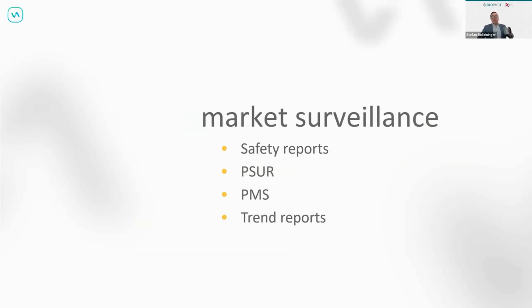So, next part is the post-market surveillance. Since the product is after the conformity assessment in the market, we need to talk a lot about the post-market surveillance system, which is very well enforced within the MDR, and it's very strongly introduced there, which is quite good and has a lot of additional information, and that's something which really helps you as a manufacturer. On one side it's a bit of a pain because you need to create documents and records. On the other side, it helps you a lot to gather data from the past, what and where you can increase or make your device better and more clear.